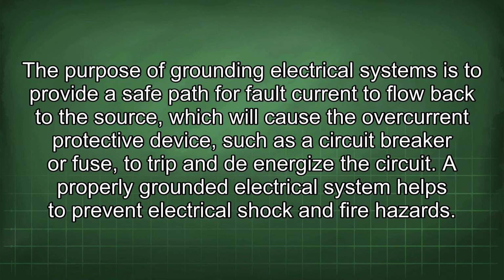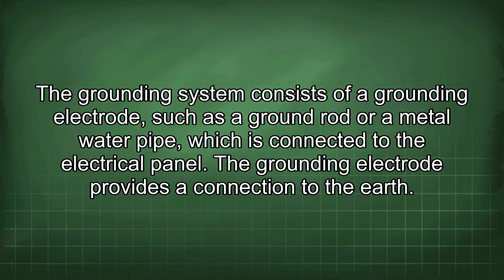The purpose of grounding electrical systems is to provide a safe path for fault current to flow back to the source, which will cause the overcurrent protective device, such as a circuit breaker or fuse, to trip and de-energize the circuit. A properly grounded electrical system helps to prevent electrical shock and fire hazards. The grounding system consists of a grounding electrode, such as a ground rod or a metal water pipe, which is connected to the electrical panel. The grounding electrode provides a connection to the earth.